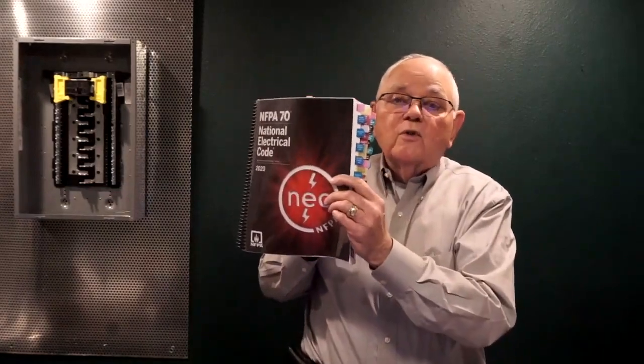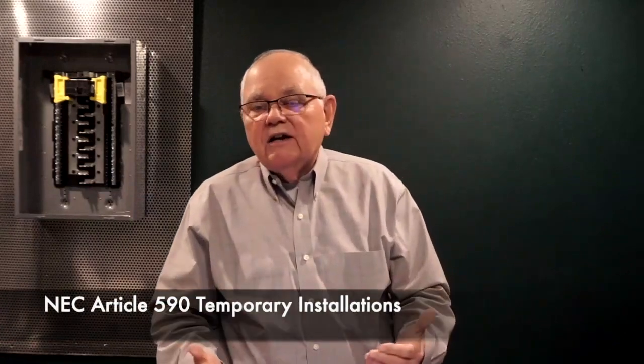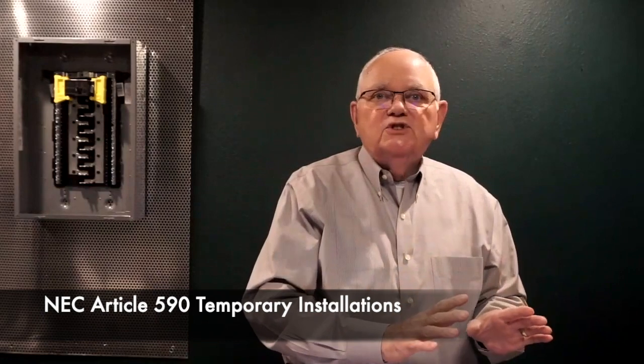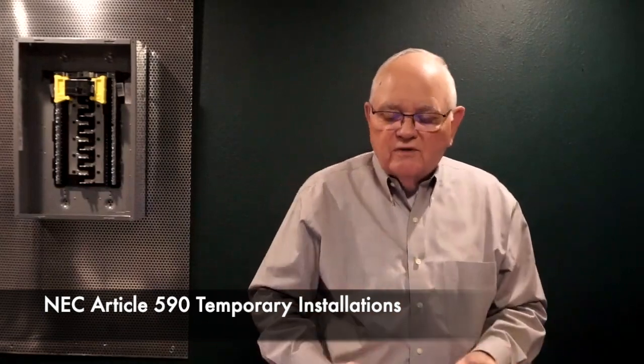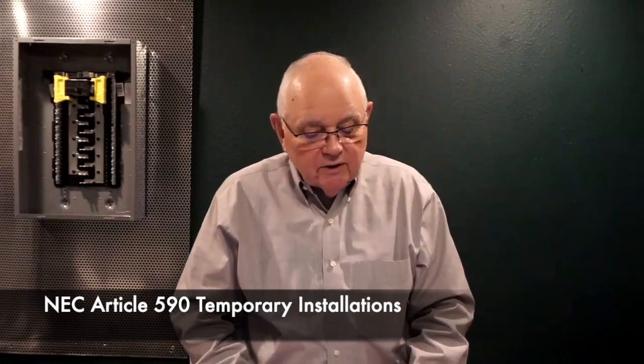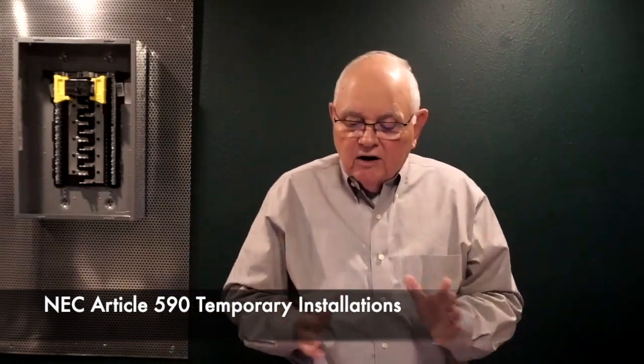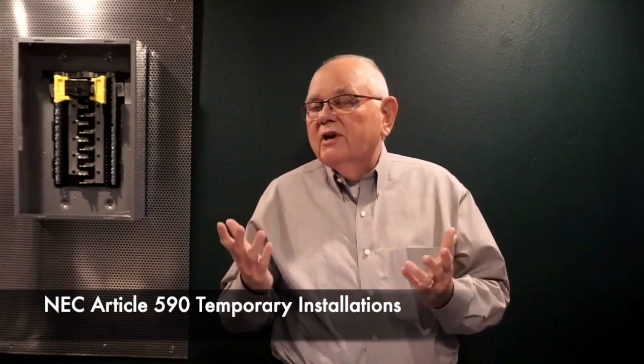But there's another place that we use GFCIs a lot, and that's if we take a look in the National Electrical Code, and once again, I'm using the current 2020 edition. If we take a look at Article 590, and by the way, there are many, many other requirements for GFCIs. In fact, we've mentioned that before in previous tech talks within the National Electrical Code. But anyway, Article 590 of the NEC is on temporary installations. And specifically, 590.1 tells us the scope of what this applies to. And it applies to temporary electric power and lighting installations. And it goes on in the next section and talks about all wiring installations. And it goes on and gets into more detail.